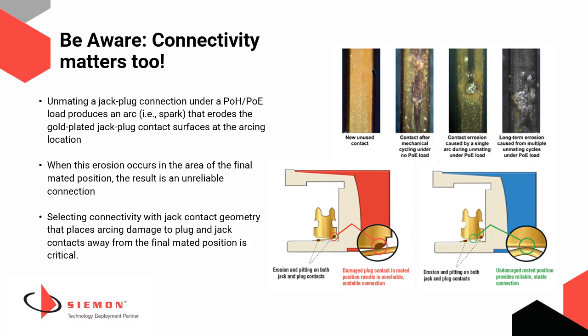Unmating a jack under load or unplugging the jack while power is running through the cable can cause arcing. Arcing is flow of electrical current through air, meaning electricity jumps from one type of connection to another, as in from copper to air back to copper. Siemon jacks with PowerGuard technology feature a patented crown jack contact shape that places arcing damage to both the plug and jack contacts away from the final mated position, allowing you to connect and disconnect to the latest remote powering applications with zero risk.